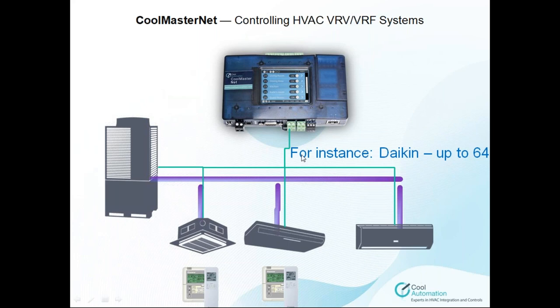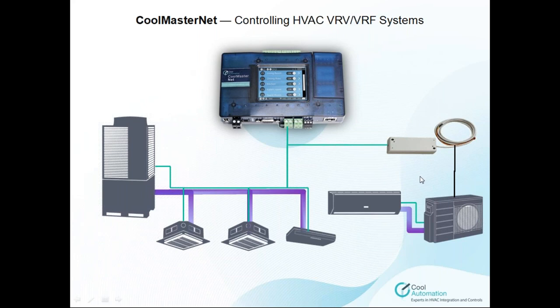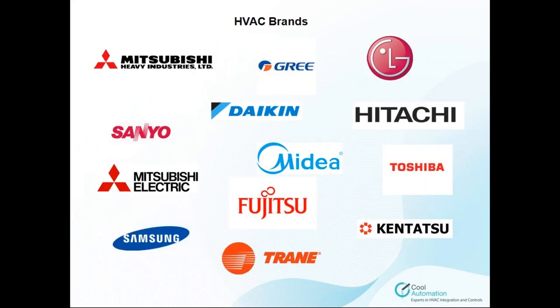CoolMasterNet is connected to the same bus, the same communication bus as exactly like indoors and outdoors. In case that you have split system and you want to connect it to CoolMasterNet as well, the only solution is to connect it through adapter. These adapters exist only in Daikin and Mitsubishi systems. If you have one of them, you will be able to connect split system to CoolMaster as well.